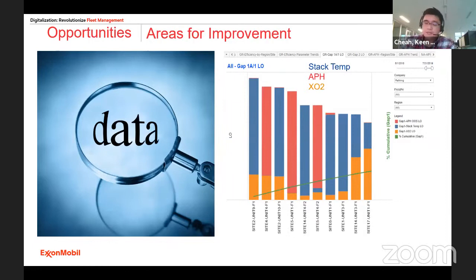For example, for the first furnace shown on the graph, the dominant cause is the high stack temperature, evident by the large blue bar. The second is the malfunctioning of the air preheater, highlighted by the gap caused by the air preheater being out of service. By quickly narrowing down the dominant cause, we can bring in the right subject matter experts to help sites identify and close the associated gaps.